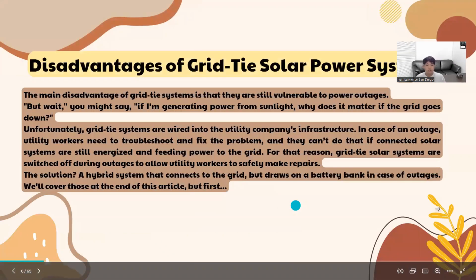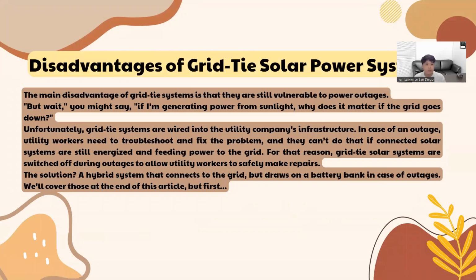Now let's talk about the disadvantages of the grid tie solar power system. The main disadvantage is that they are still vulnerable to power outages. But you might say, if I'm generating power from sunlight, why does it matter if the grid is down? Unfortunately, grid tie systems are wired into the utility company's infrastructure. In case of an outage, utility workers need to troubleshoot and fix the problem, and they can't do that if connected solar systems are still energized and feeding power to the grid. For that reason, grid tie solar systems are switched off during outages to allow utility workers to safely make repairs.